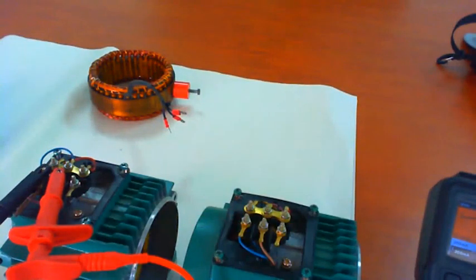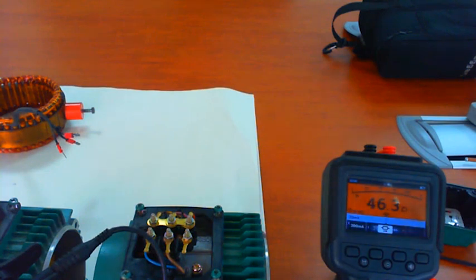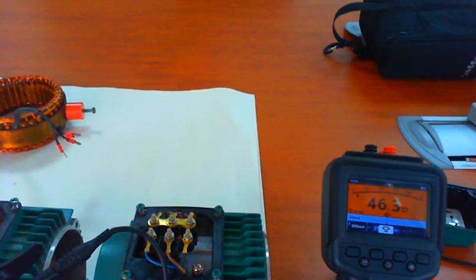U to V, yeah, 46.1. V to W, 48.6. W to U, 46.3. So the two windings, from a resistance point of view, are the same or very similar. That reversed phase hasn't affected resistance because the amount of copper in the circuit hasn't changed, it's identical. But inductance is affected by coil shape and many other reasons, and inductance is able to pick up that reverse connection problem. So if you're just testing using winding resistance and IR testing on your motors, if you're a motor repair company, you can very easily send out a motor with a reversed phase.